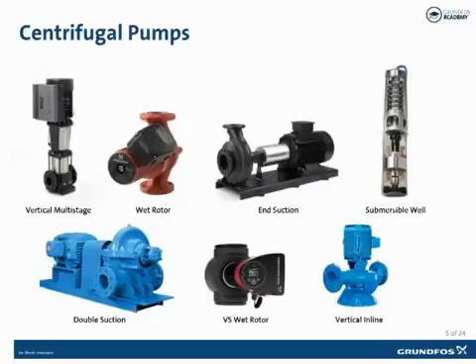Additional HVAC pump types include submersible well pumps for ground water and water source heat pumps, double suction for primary and condenser water loops, variable speed wet rotor pumps for boiler, secondary, and tertiary loops as well as coil pumps, and vertical inlines for primary, secondary, tertiary, and condenser water loops. Detailed specific application guidelines and feature benefits of these pumps are discussed in subsequent modules.